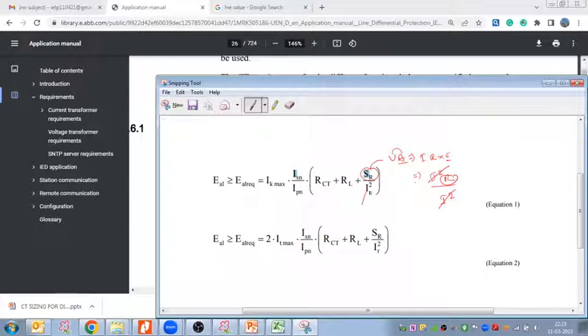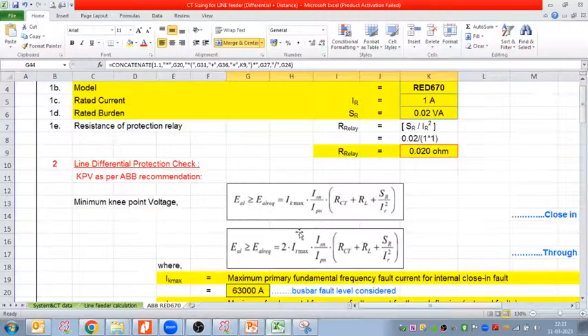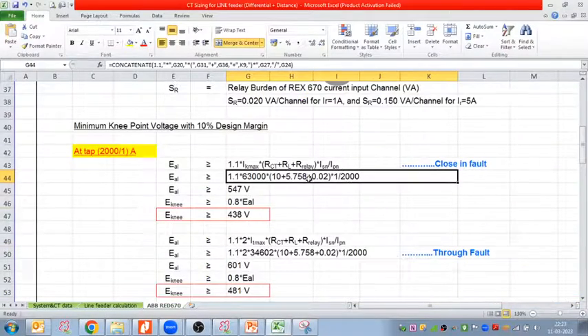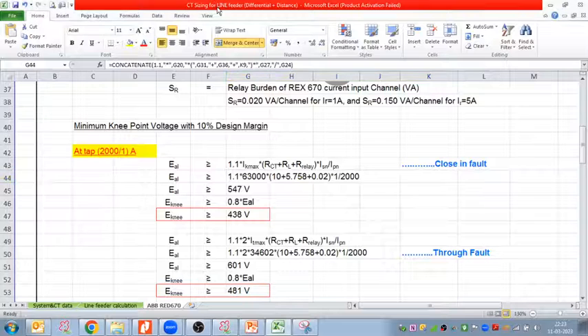So that I am putting here. VA divided by I square is only R, so that same value I am putting here, R of the relay. If your VA is 0.02 and your A is 1, then the burden would be 0.02, so the R is 0.02.